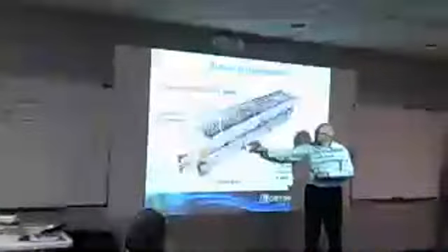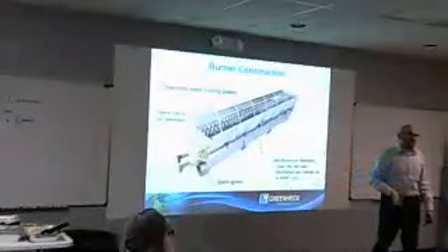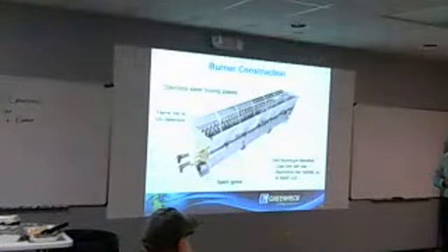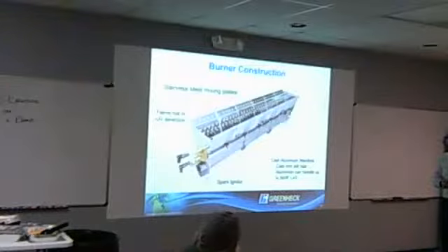The burner is made in different modules or different sections. You can see them bolted together. Each one usually is about 400 MBH. So if we had 1600, each section I think is maybe a foot or 8 inches. It's about, if I remember right, about that big. So maybe it's a foot. But we would assemble them appropriately to achieve the MBH required, depending on the air volume and the required heating capacity. Says aluminum can handle LAT.